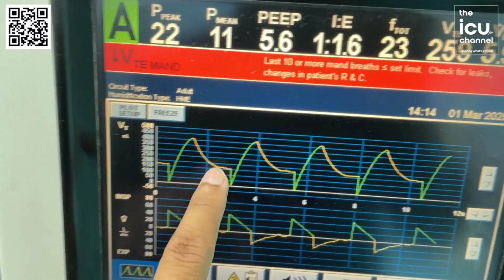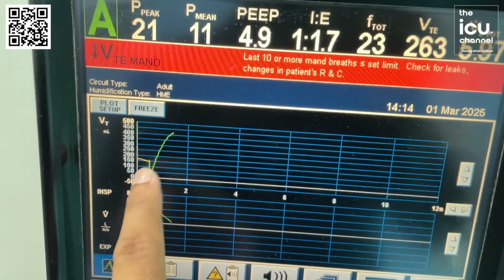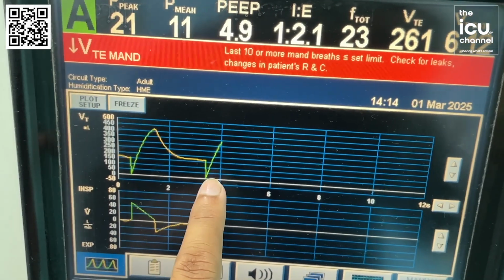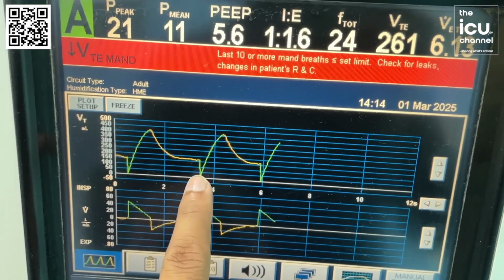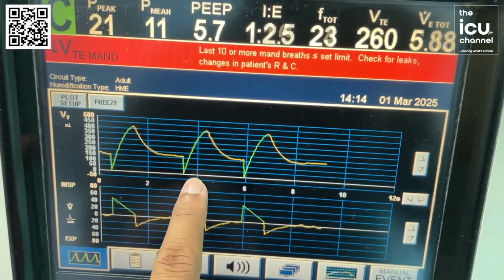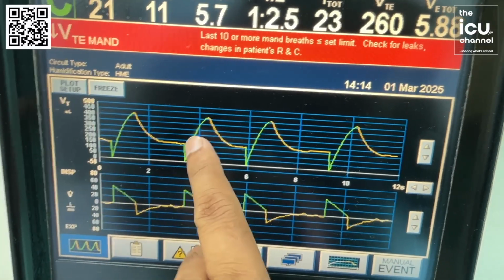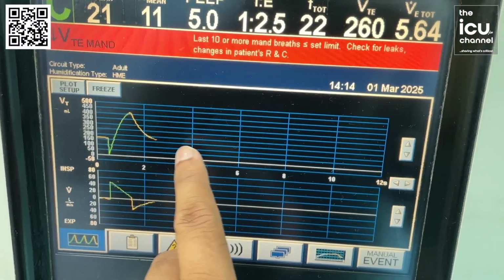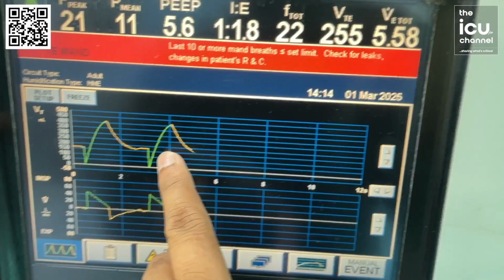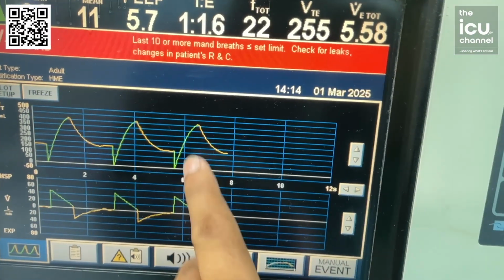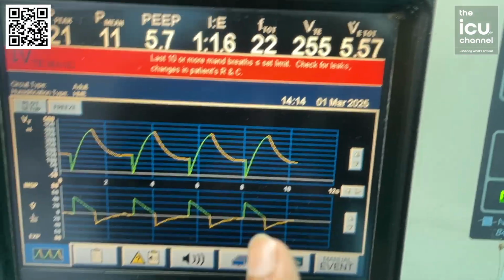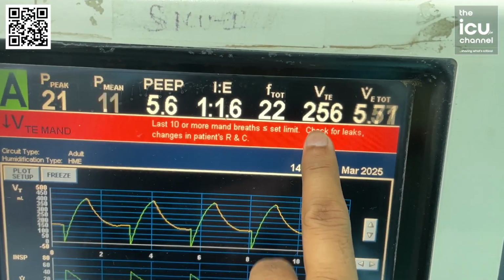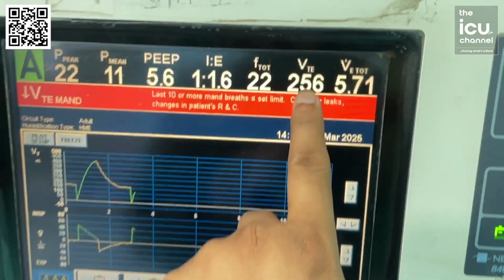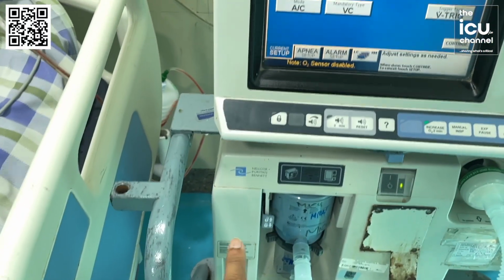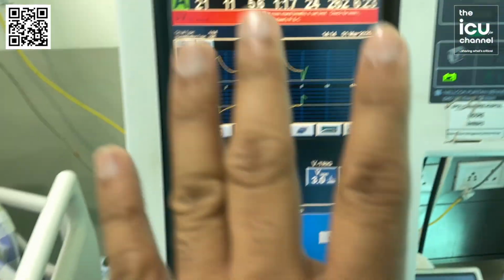On the expiratory limb, you can see it is not touching the baseline. This is inspiration, and the expiratory limb is getting closed in between as a vertical line. You see the expiratory limb is getting cut off as a vertical line. That means there is some leak in the circuit. This sudden cutoff shows that there is a leak in the circuit. If there is a leak, the tidal volume which the flow sensor is receiving at the expiratory flow is telling that we are not providing sufficient tidal volume to the patient.